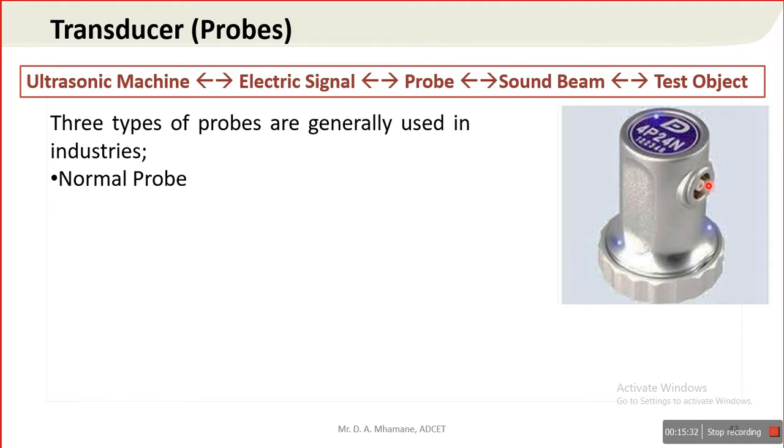This slot is given for connecting the connectors to the instrument. So normal probe needs a single connector for connection, because normal probe itself transmits and receives the ultrasound pulse. The single crystal present inside the probe receives as well as transmits the sound wave, so it requires a single connector.